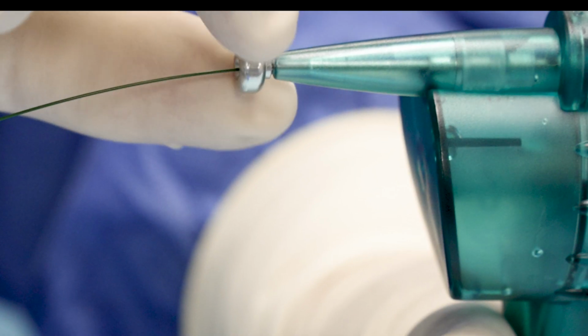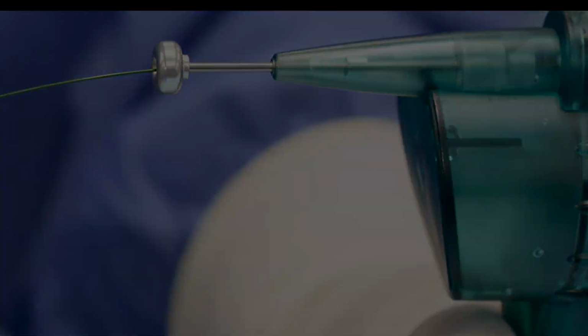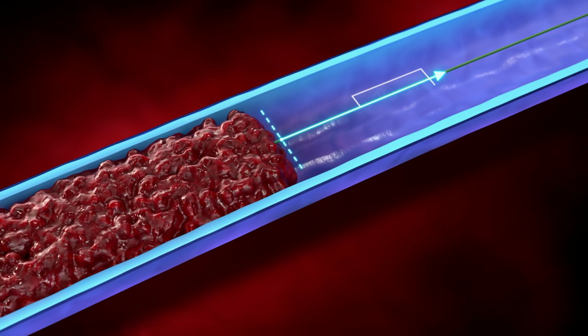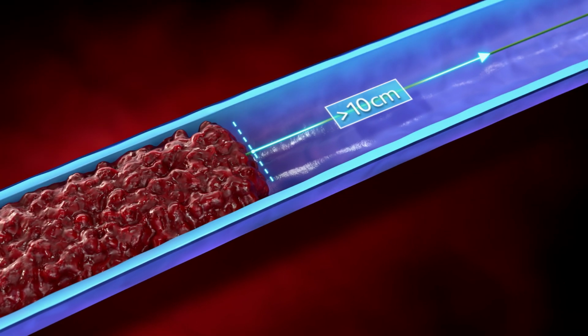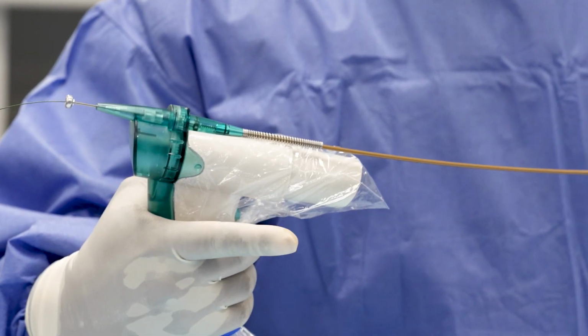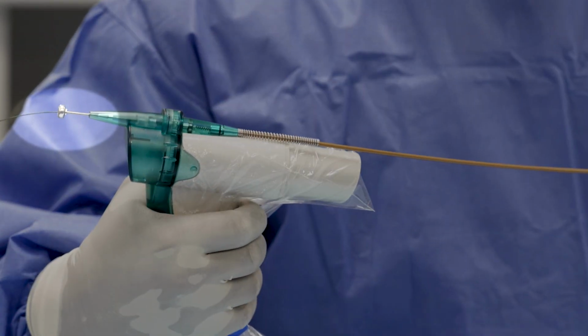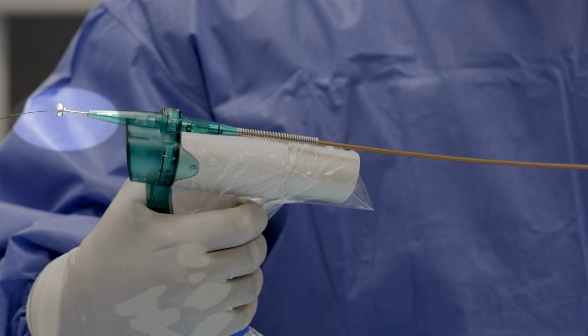Step 8. Close guide wire adapter. Close the guide wire adapter by pulling it back. Ensure the guide wire tip is at least 10 centimeters past the occlusion. Note: the guide wire adapter must be in the working position when the motor is active.